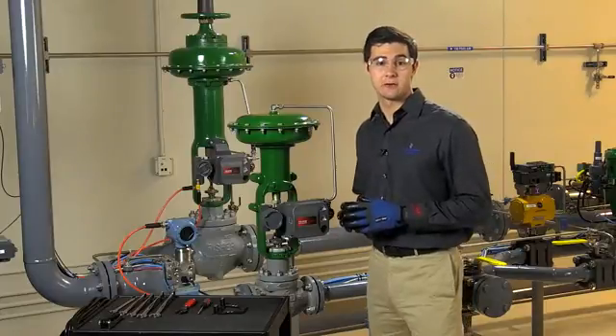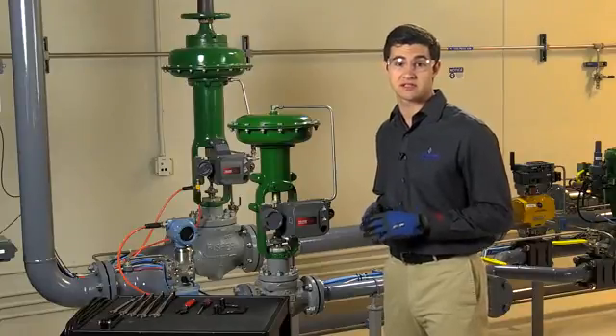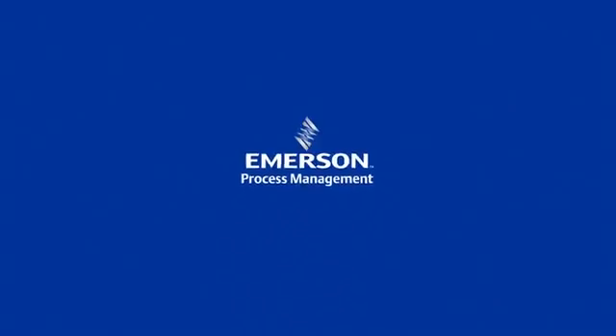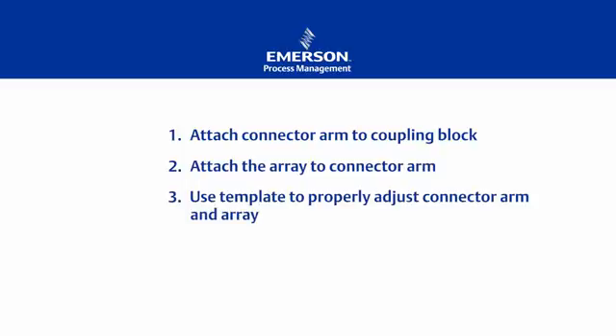We've now learned how to mount a FIELDVUE DVC6200 digital valve controller to a Fisher type 657 or 667 size I actuator, using the integrated mounting pad on the yoke. Let's review the steps we took. First, we installed the connector arm to the coupling block — remember to relieve the pressure in the actuator when using a 657 size I, or use air to lift the valve plug off its seat with a 667 size I. Second, we attached the magnetic array to the connector arm. Third, we used the mounting template to properly adjust the connector arm and magnetic array.